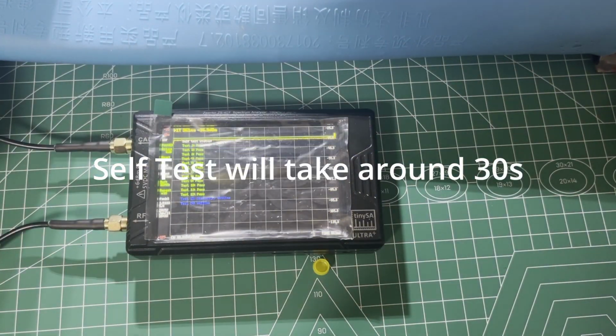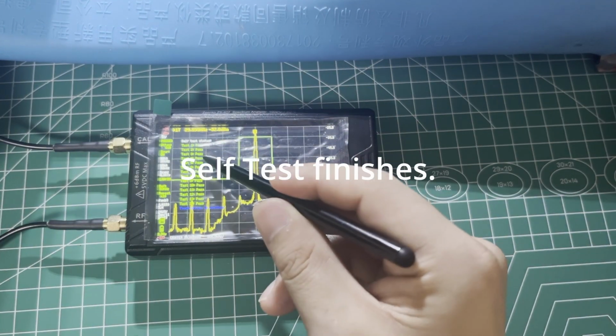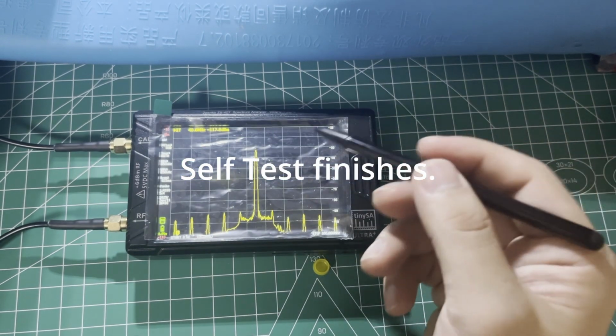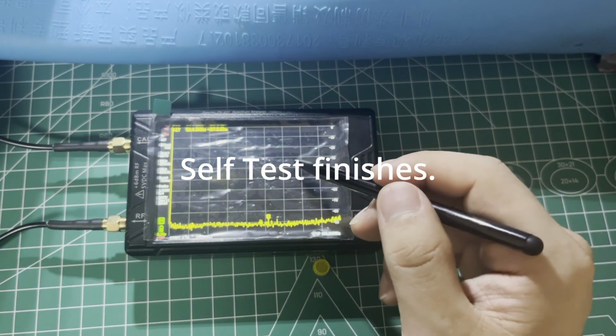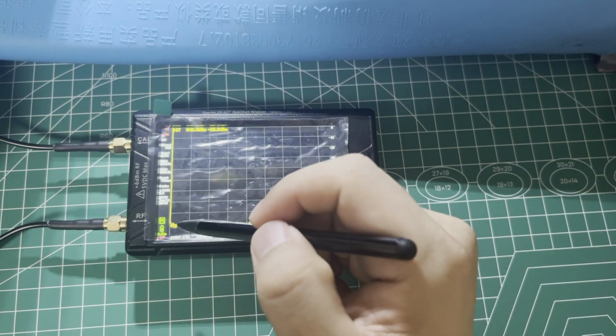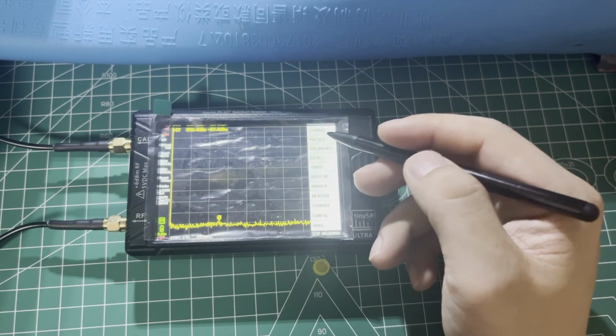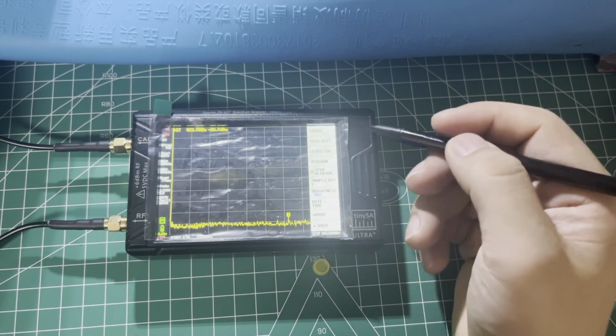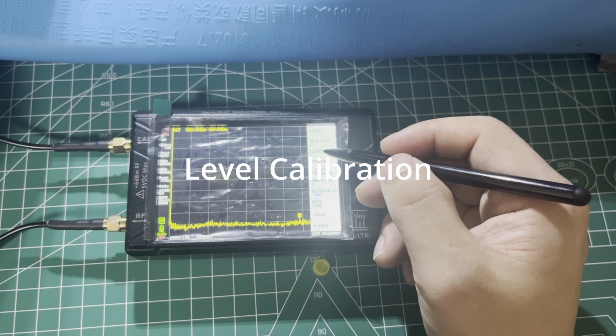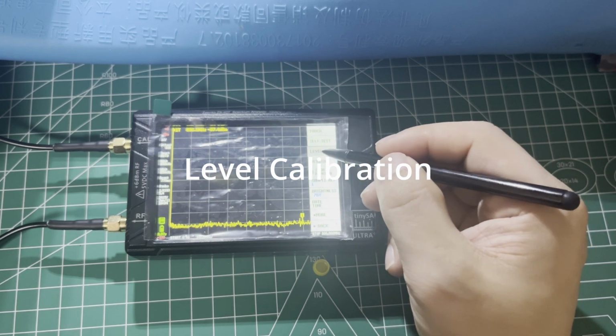Self-test will take around 30 seconds. But self-test is not a calibration, so you will still see the red letters on the left. So let's go to the level calibration.